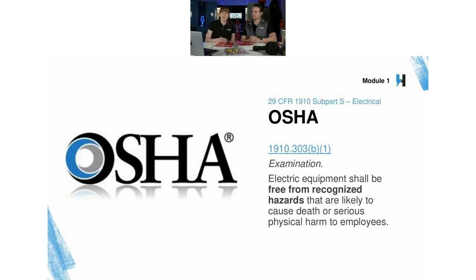And in section 303 of that 1910, there's a part called examination. It says that electrical equipment shall be free from recognized hazards that are likely to cause death or serious physical harm to employees. So since arc flash, shock, electrical fires, anything that goes with electrical equipment, if it's not maintained well, is considered a recognized hazard, that's where we start to understand that maintaining your equipment does fall within this requirement of having it free from recognized hazards. Not maintained well can cause hazards. We've got to follow this now.